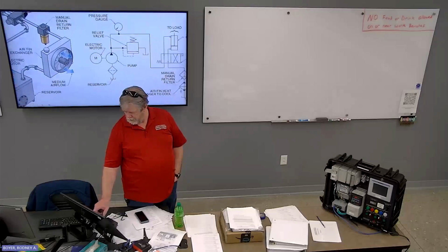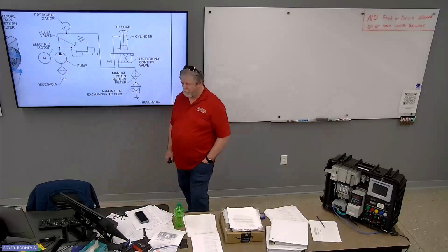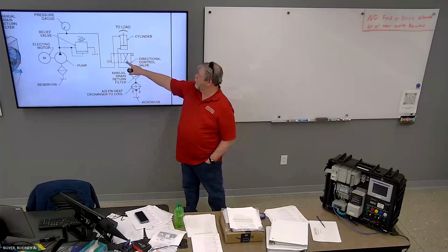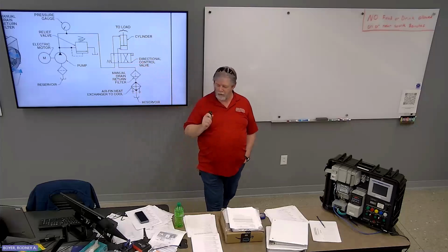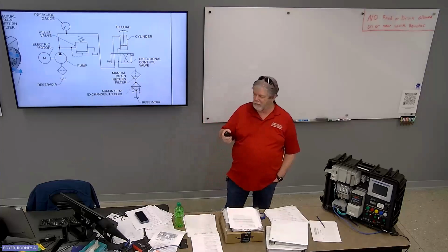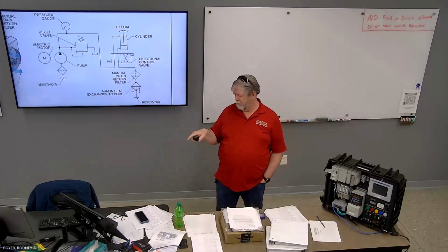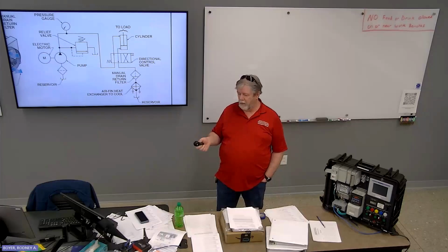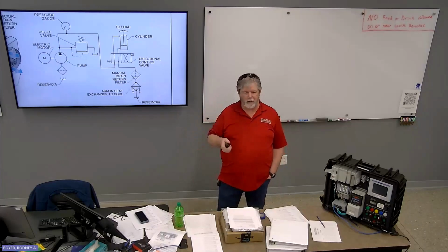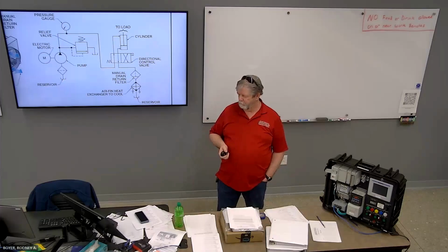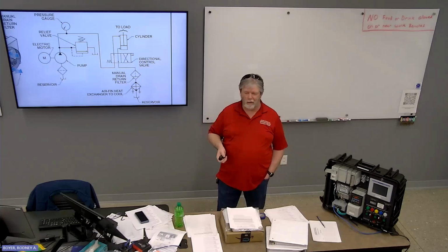Yeah. It's exactly the same thing, only it's solenoid operated, spring return. So whenever you energize the solenoid, it'll retract. Whenever you de-energize the solenoid, the spring is going to push it back the other direction and it'll extend. No. Its default is to retract, isn't it? Yeah. So when you energize the solenoid, it'll extend. Whenever you release the solenoid, it'll retract.